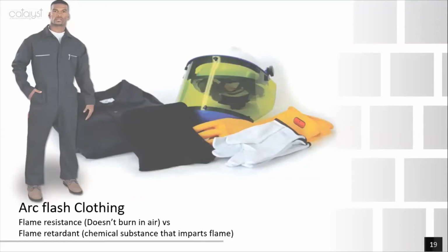There are a couple of other things you should look for when buying arc flash clothing. The material should be inherent FR. Arc rated should be written right on it. If it's a shirt, it'll often be on the collar. It'll be inside the breast of a coat. On the pants, it'll be towards the back or the side. Buttons and zippers should be properly protected. The thread used, and this goes for hemming or shortening, any alterations, logos, must be FR.